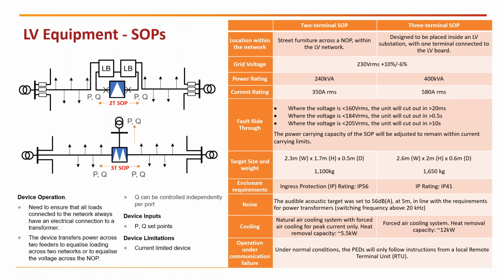One key specification is that the 2-terminal SOP is street furniture, which is one of the interesting things of the device. So a lot of flexibility. You can put it on a pavement, and that will enable 2 secondary substations to help each other when they're struggling, so as to defer reinforcement of one.